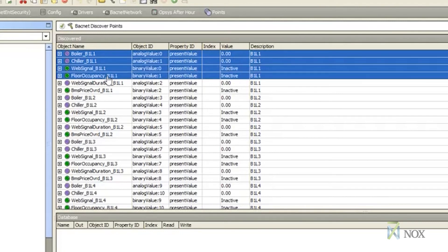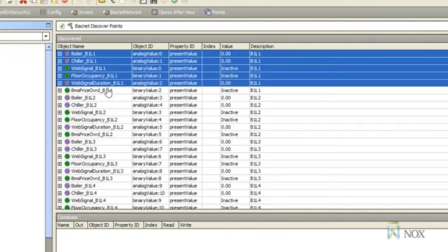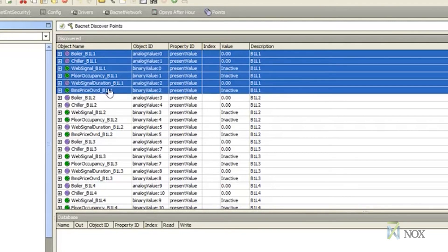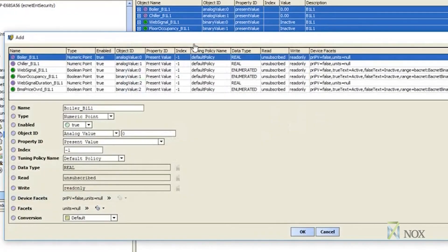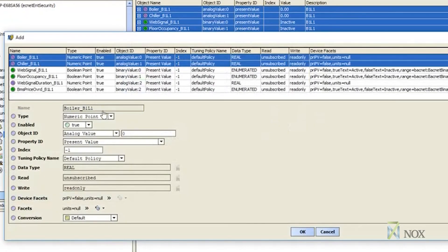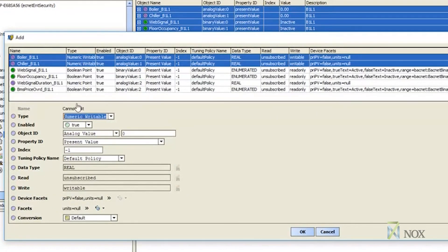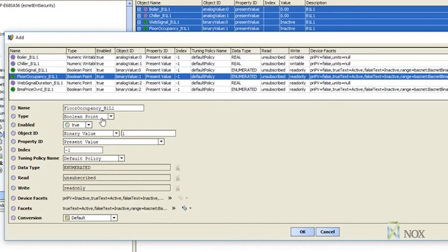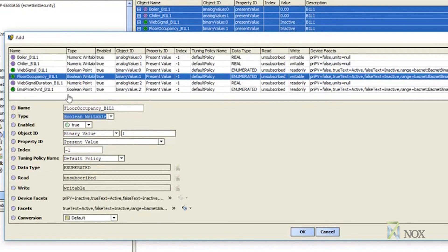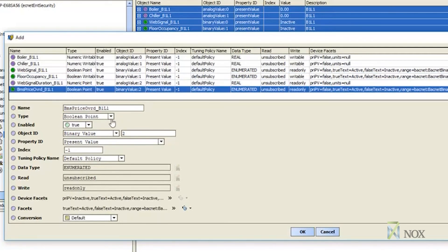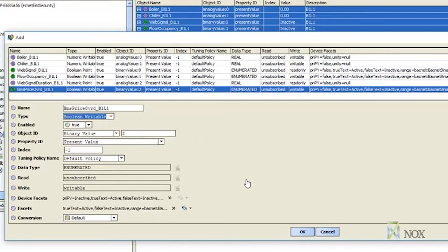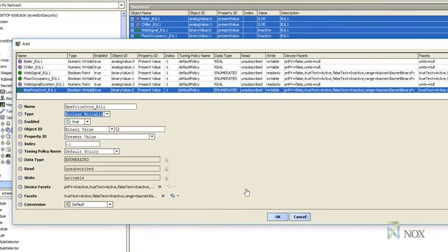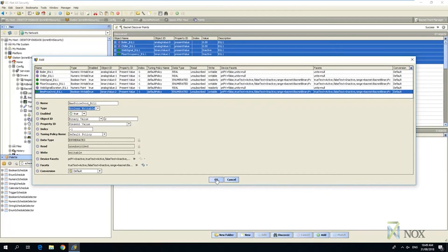Two analog values, boiler and chiller. These are optional points and are only used when a building charges for the chiller consumption or charges for the boiler consumption. The floor occupancy points are only used if physical buttons are installed on site to enable the after hours air conditioning. This is also an optional point. The web signal point is a compulsory point that is used to enable the after hours air conditioning.